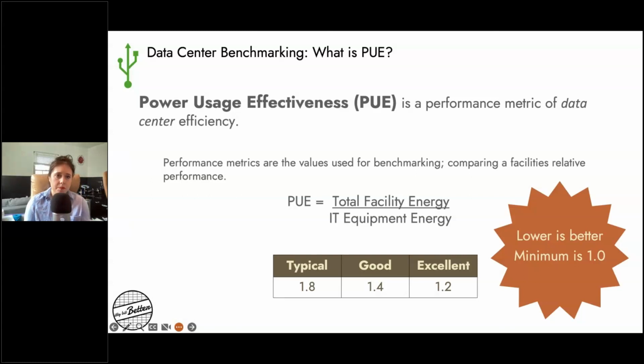First off, PUE, power usage effectiveness, is an industry-wide term for data centers. It's the performance metric of data center efficiency, and it's a really simple ratio: total facility energy over IT equipment energy. If you remember from the pie chart, IT energy and HVAC energy is almost a 50-50 split. So with this simple ratio, you can quickly get a good idea of how much energy your IT and HVAC equipment is using compared to your overall data center energy. At the bottom, you have your benchmarking metrics, what's typical, what's excellent, to give you an idea of where your data center stands.